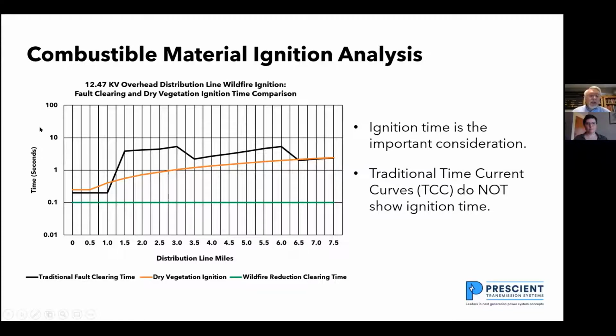And the red line here, this is the ignition time of dry vegetation. And you can see that between mile 1.5 and mile 6.5, dry vegetation is likely to ignite before the fault is cleared. So what I want to do is I want to come up with a wildfire reduction clearing time, the green line down here. The green line shows faults cleared in 100 milliseconds. And the way I get faults cleared in 100 milliseconds is the first thing I do is I disable reclosing.